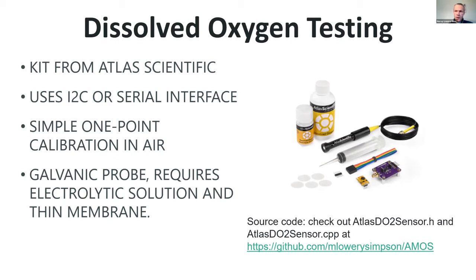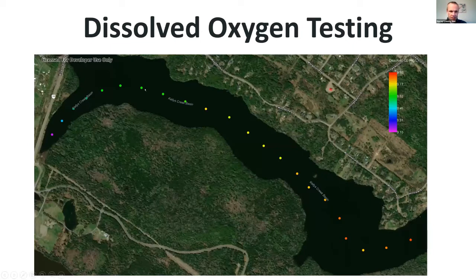I found it worked pretty well. The only drawback, I think, was that the membrane, it's probably about the thickness of a contact lens. It would tend to get nicked if you're in really shallow water and dragging the end of the probe on a sandy bottom or rocks and that sort of thing. So that was a bit of a problem. And of course, when there's any sort of nick in this membrane, you lose your electrolyte solution pretty quickly and it goes out of calibration. So I learned to kind of stick to the middle of the river for dissolved oxygen testing.